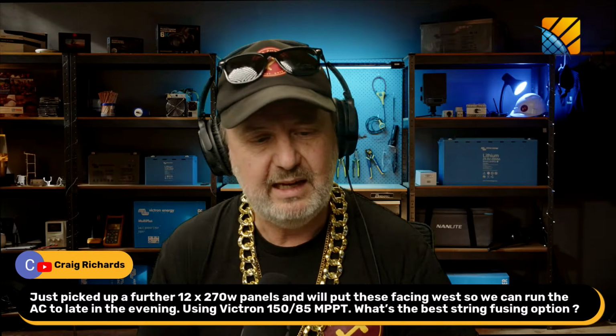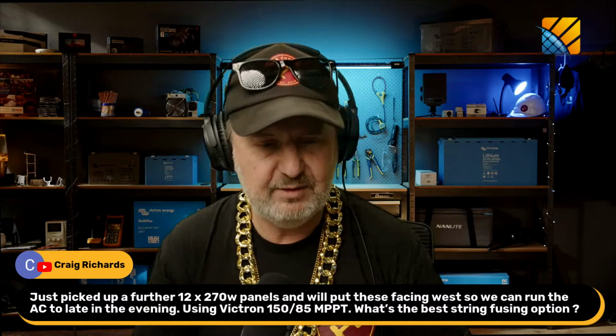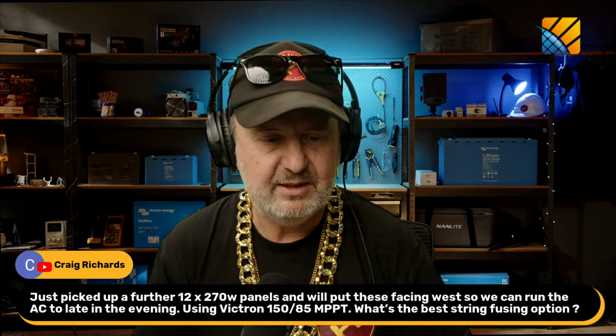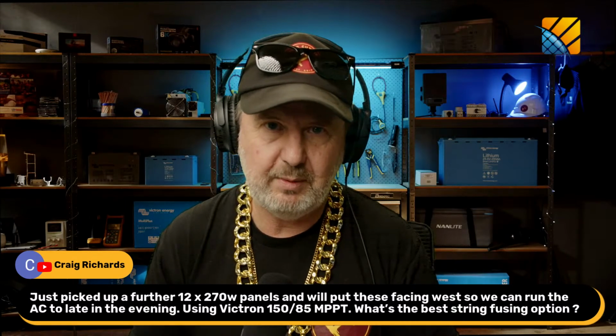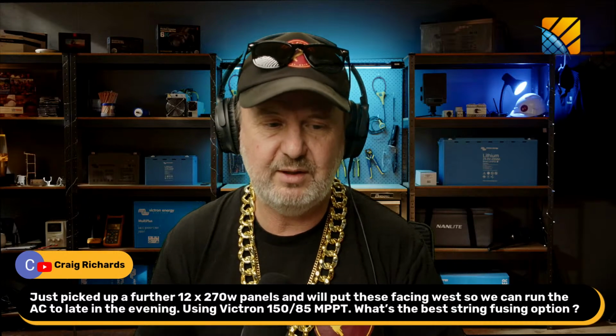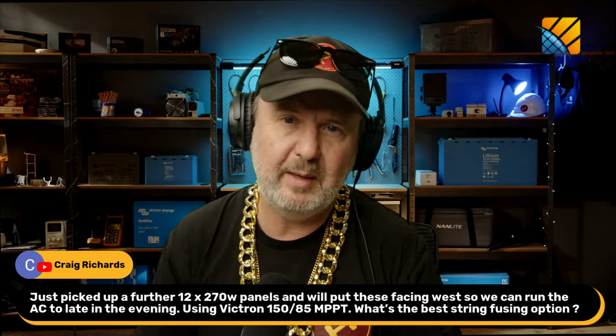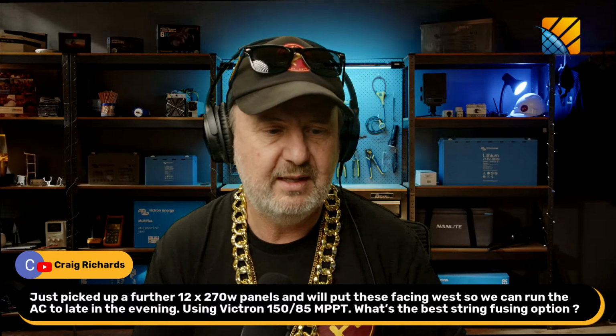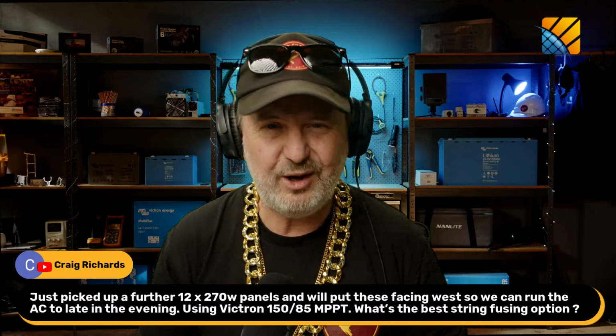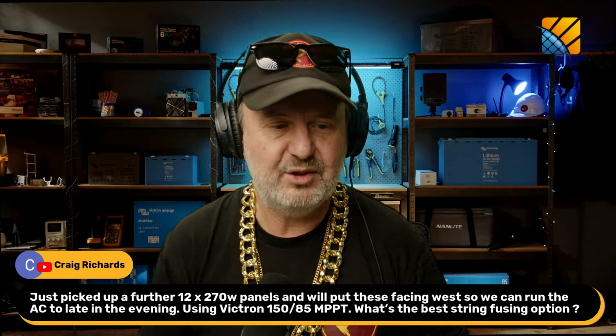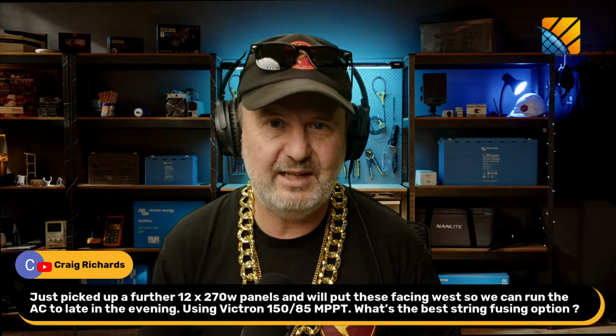Okay, well Craig, a few things to consider then. You're talking about using a maximum power point tracking charge controller, and the Victron, excellent product, has a maximum input voltage of 150 volts. So you'd have to make sure that under the coldest operating conditions, the strings were short enough not to exceed 150 volts.